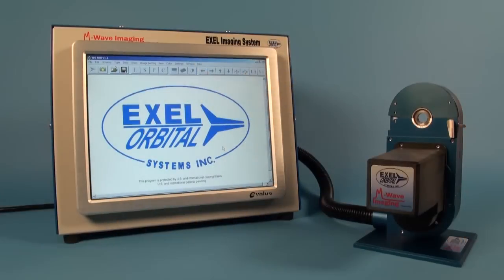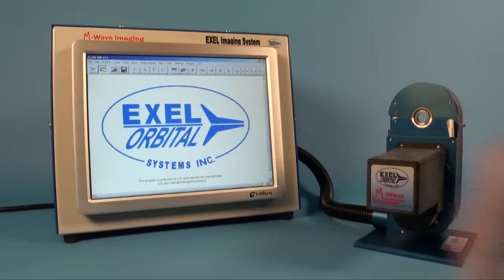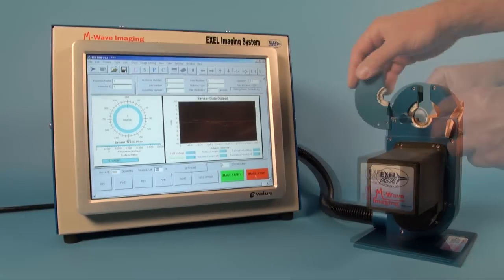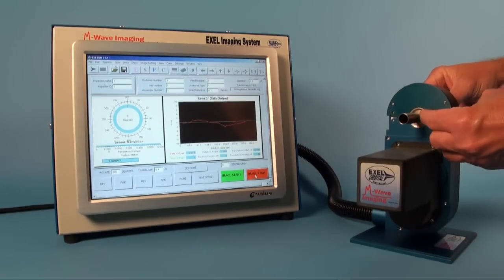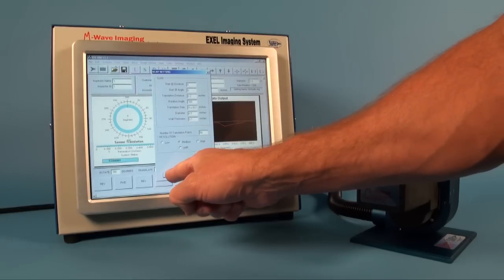Imaging a component is easy. Simply fixture the component or assembly into the imaging head, positioning the flaw in the scanning zone. In this case, the flaw is a 30 thousandths of an inch long by 15 thousandths of an inch deep EDM notch, simulating a crack.